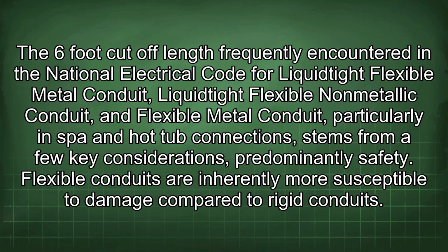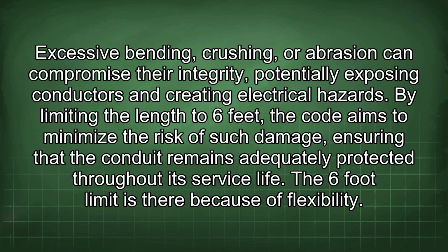The 6-foot cut-off length frequently encountered in the National Electrical Code for liquid-tight flexible metal conduit, liquid-tight flexible non-metallic conduit, and flexible metal conduit, particularly in spa and hot tub connections, stems from a few key considerations, predominantly safety. Flexible conduits are inherently more susceptible to damage compared to rigid conduits. Excessive bending, crushing, or abrasion can compromise their integrity, potentially exposing conductors and creating electrical hazards. By limiting the length to 6 feet, the code aims to minimize the risk of such damage, ensuring that the conduit remains adequately protected throughout its service life.